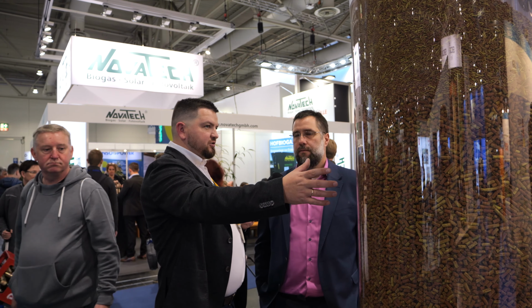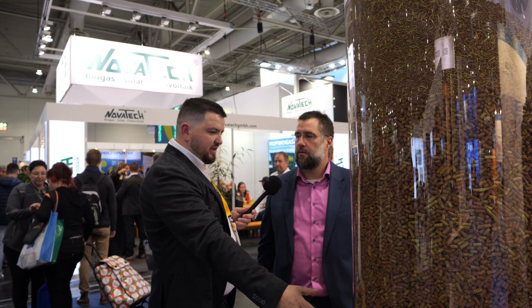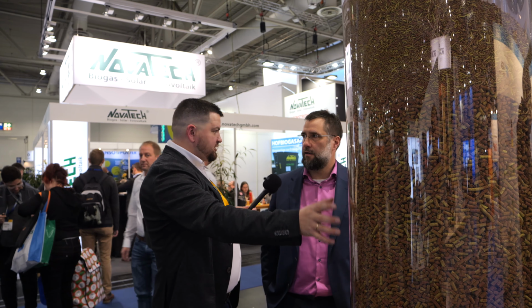Let's say we have a stainless steel tank which we use as a filter. Then we fill it up with the bigger, smaller and the very small at the top. Yes, that's the right way. And this helps slow down the gas while it gets cleaned. Or rather, not to slow down. You can slow it down by the dimension of the tank, so you have a difference in flow speed. This is just to have a pressure drop, and with this pressure drop you have a better distribution.